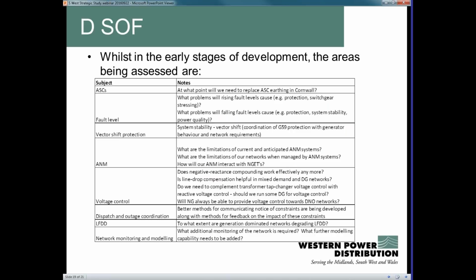Vector shift protection is a particular form of loss of mains protection. We put loss of mains protection on generation connected to the network to ensure that we end up with a safe and secure network should things happen and go wrong. There is some concern over the stability of that, and we do need to look at those issues in terms of long term, whether that continues to be the right solution, or whether there are other things we need to do.